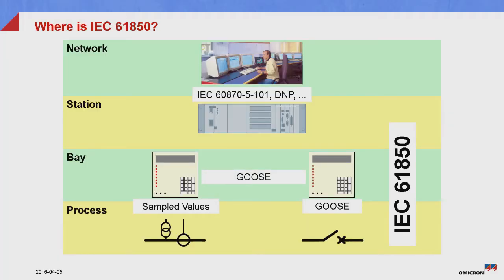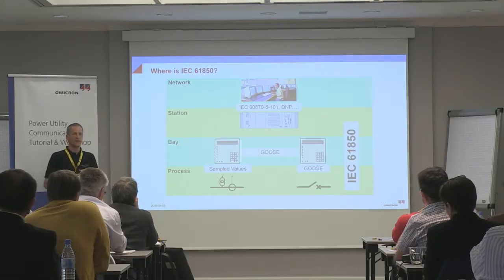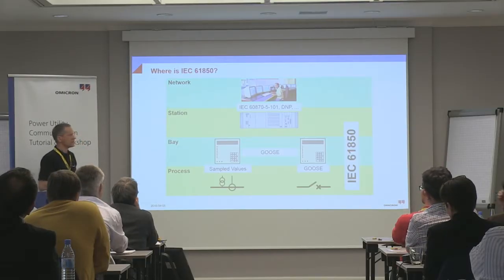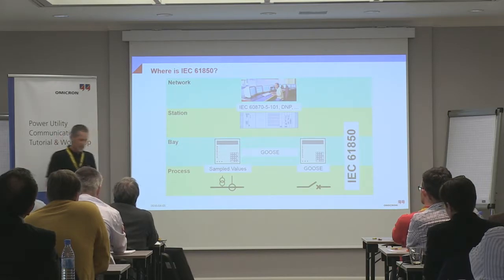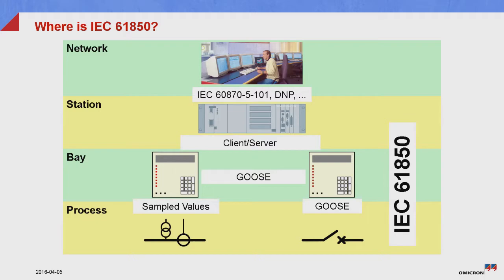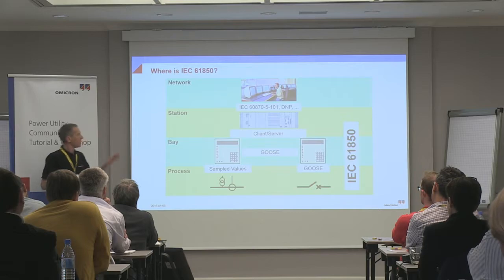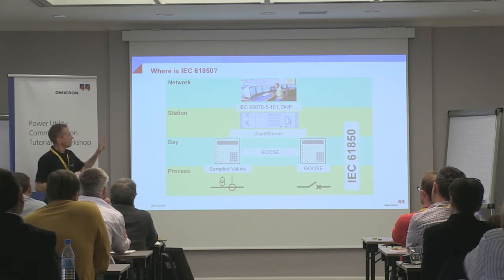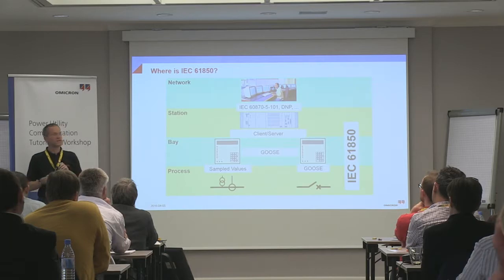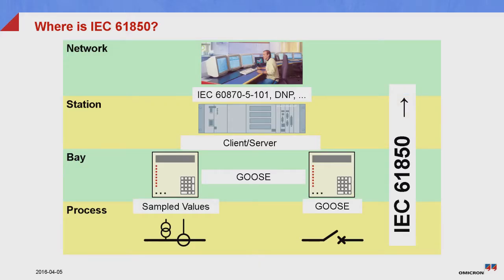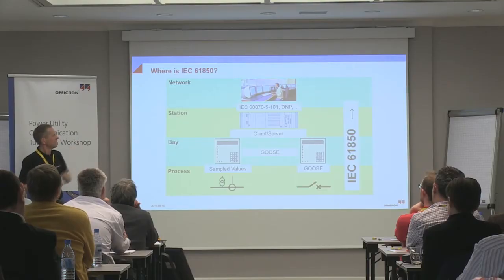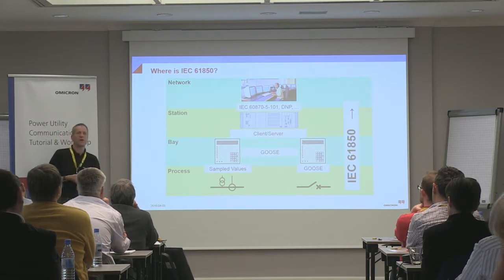And, which is already very well established, the peer-to-peer communication on the bay level between the IEDs via GOOSE messaging. Up to the station controller, we have this client-server protocol now available. Up there, there is more or less the same structure in place that we had before, but as Christoph has also indicated, IEC 61850 is leaving the substation. The scope will be extended and will go upwards as well.